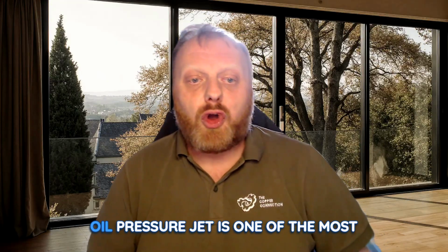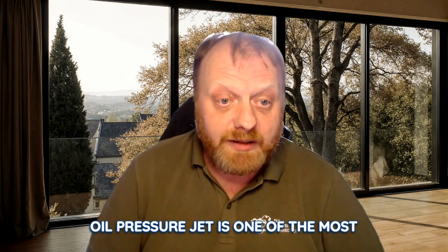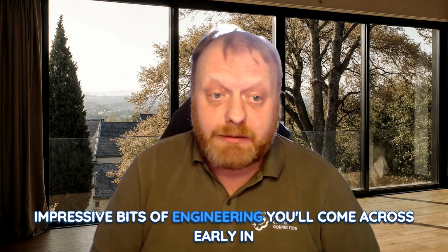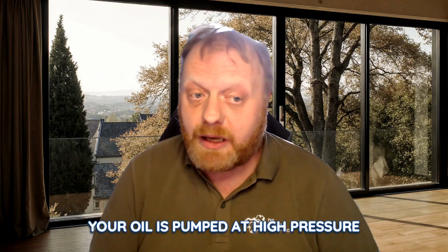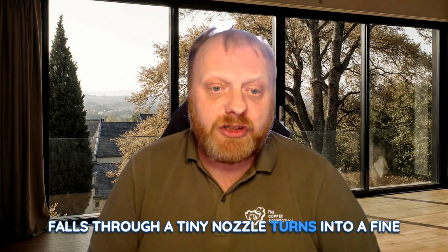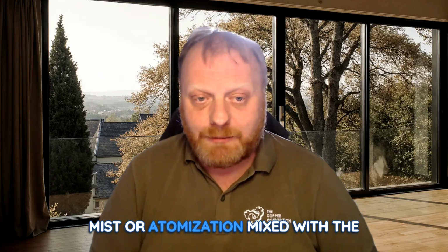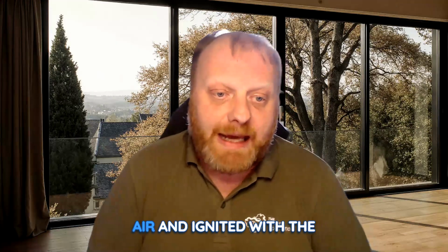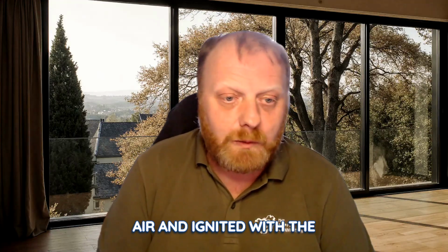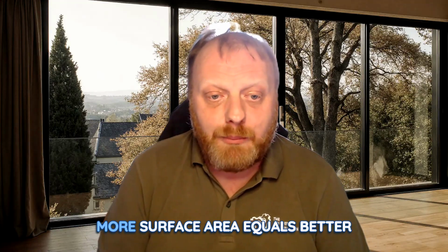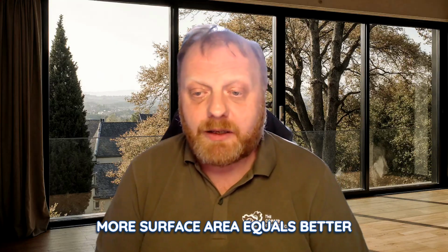Now let's talk oil. Pressure jet burners. This is one of the most impressive bits of engineering you'll come across early in your career. Oil is pumped at high pressure, forced through a tiny nozzle, turned into a fine mist, or atomization, mixed with the air and ignited with electrodes. The fine mist is key. More surface area equals better combustion.